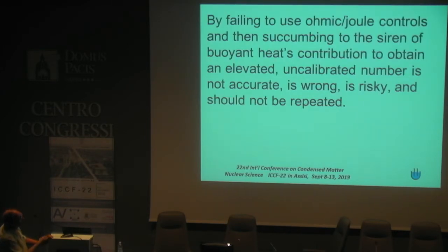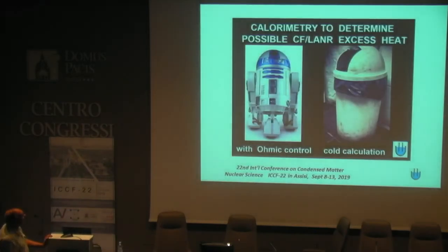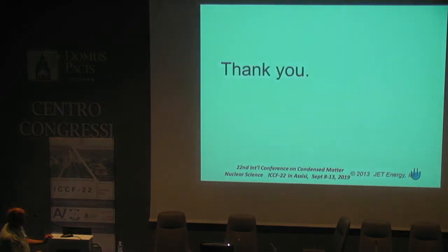And the reason I point this out is we've had enough trouble with skeptics attacking us over the last 30 years. Let's give them semi-quantitatively accurate data. And one other thing you want to do is use an OHMIC control right where your source is. I really recommend that when you do calorimetry, put an OHMIC control where the active element is. Put a square wave in. What could be easier than putting in a simple square wave? And if out of your calorimetry you don't get a square wave, don't trust your calorimeter. That's a test both for calibrating and to see if your calorimeter works. Thank you.